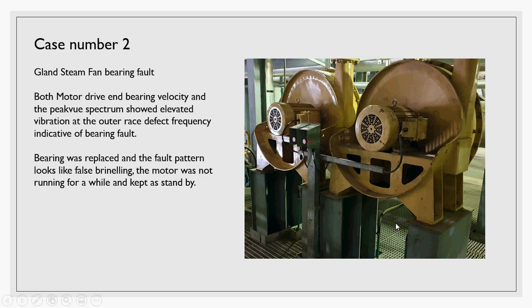Both the motor drive end bearing velocity and PeakVue spectrum showed elevated vibration at the outer race bearing defect frequency, which was indicative of a bearing fault. The bearing was replaced and the fault pattern looks like false brinelling. It's very important when you find inner race, outer race, cage, or rolling element bearing fault in your spectrum and take the decision to replace the bearing — please keep the bearing, don't throw it away.